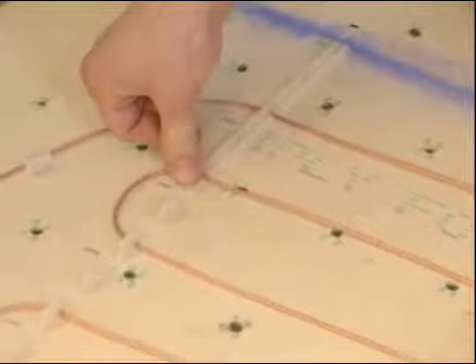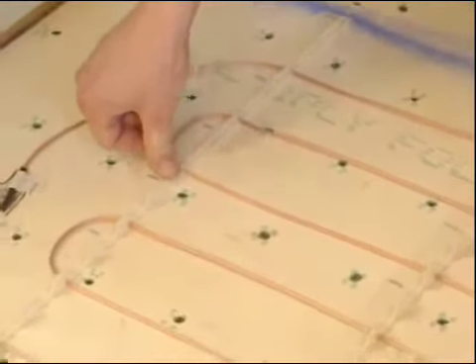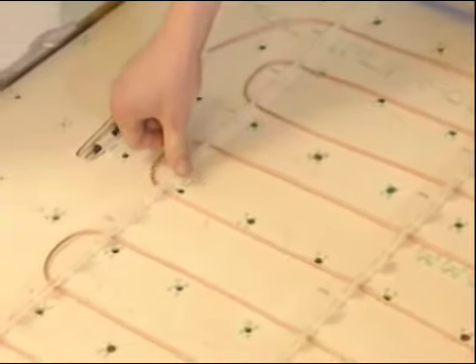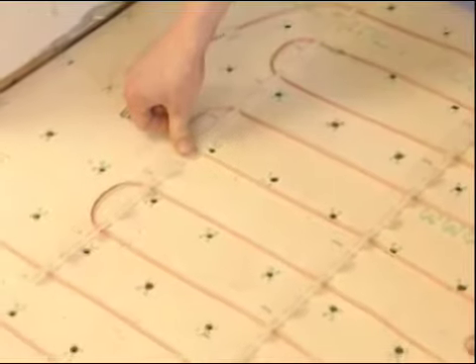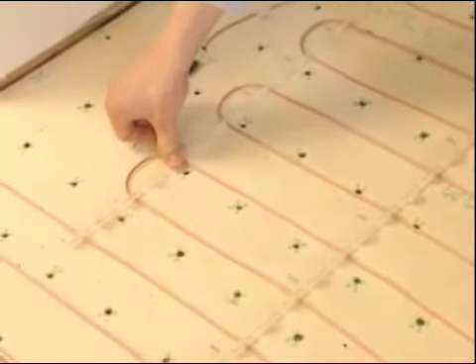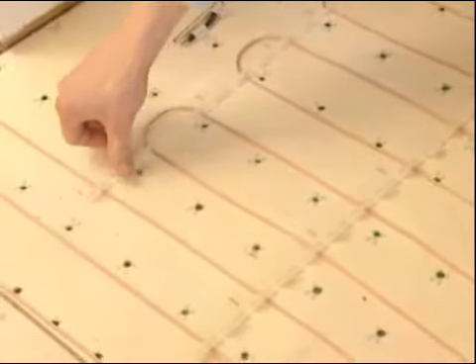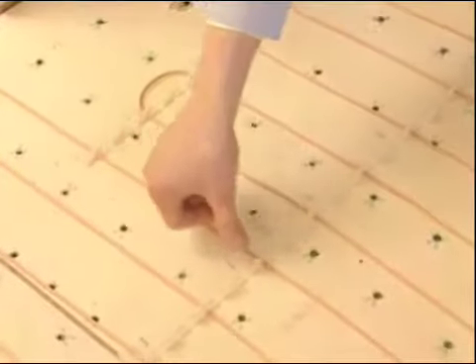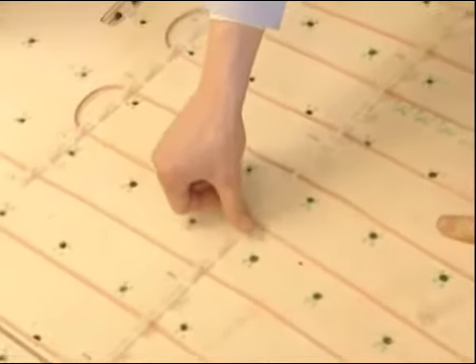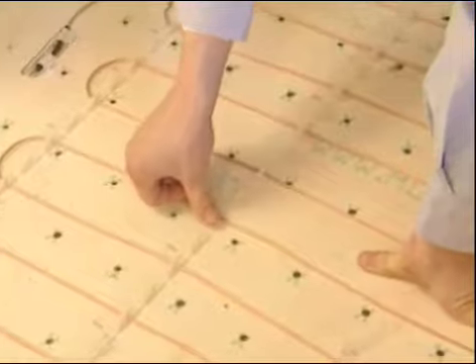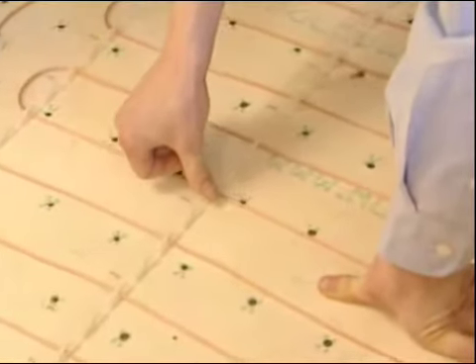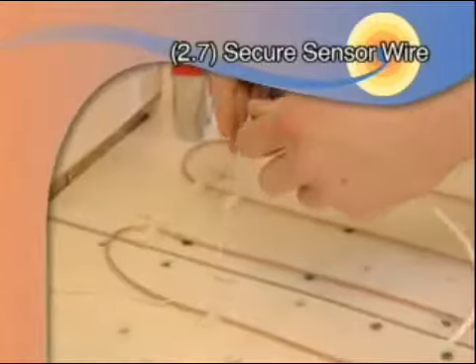Once the cable layout is completed, close all hinged clips, including the hinged clips not used, to securely fasten the cable to the floor and flatten the height of the system prior to application of the thin set. Use additional clips provided to fasten down any part of the cable that is not snug to the floor.